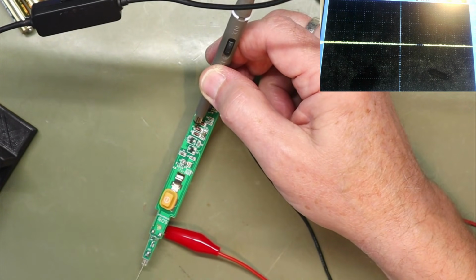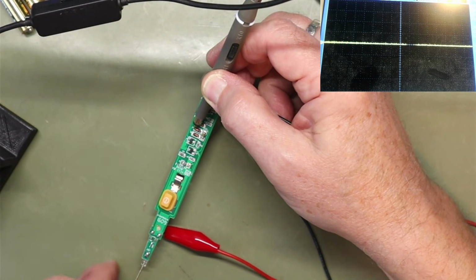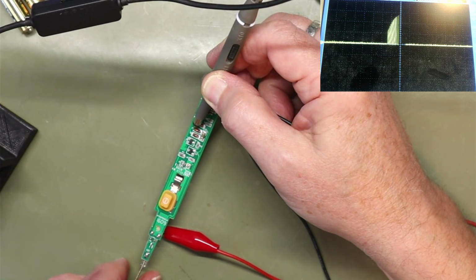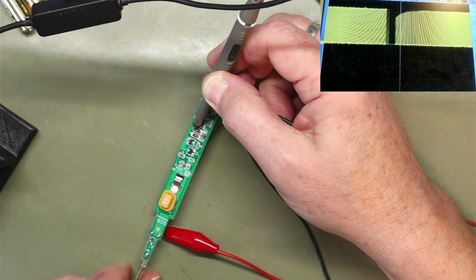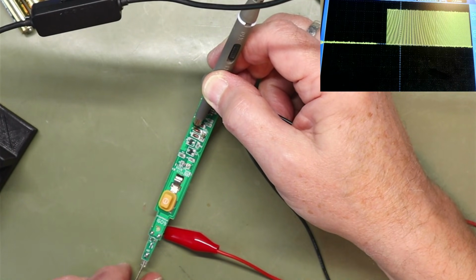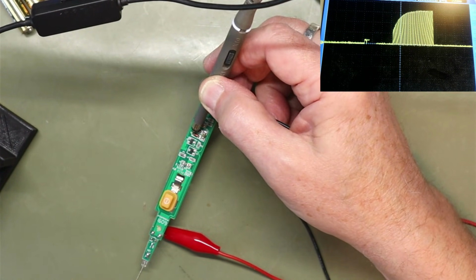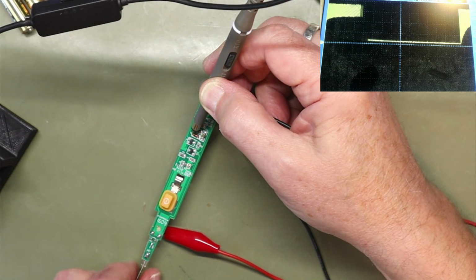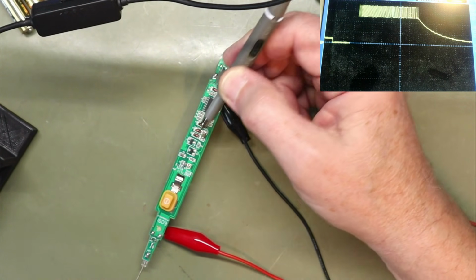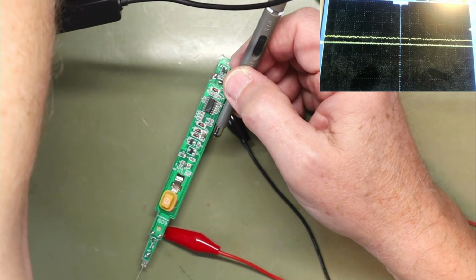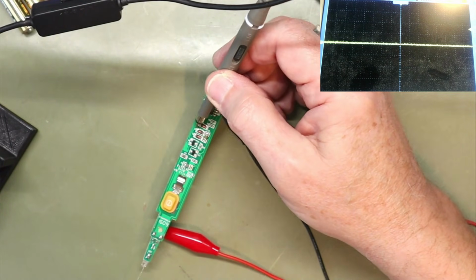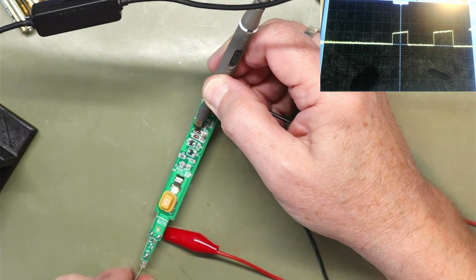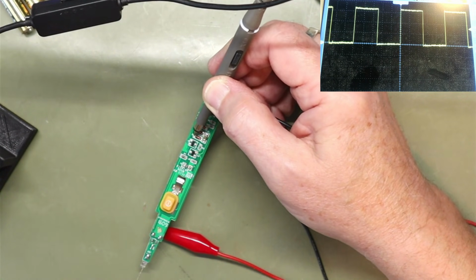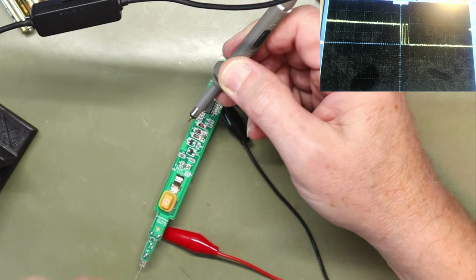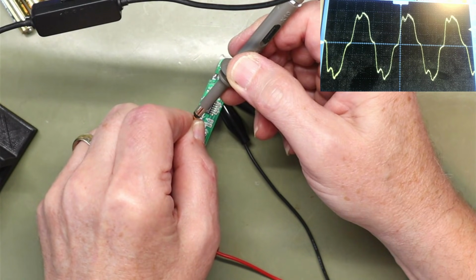if I put the scope on here, you'll see as I bring my hand in and bring some mains signal towards it, if I touch the tip, there it goes, it starts to oscillate because it's picking up the mains. And then on the other one it's doing the same again, but it looks sort of slightly different because of the way the circuit's configured. So that shows you, if I actually slow it down to about 4 milliseconds, you'll actually see that what comes up is 50 Hertz. Now it's a 50 Hertz square wave. If I actually hold the tip, you see that there's the mains it's picking up off me.